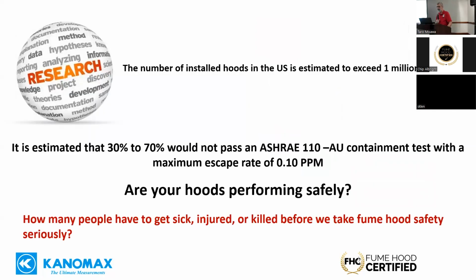So there's something in excess of 1 million hoods installed in the United States. And different people have made guesses. EPA did a little bit at one time, but it's estimated that 30% to 70% of that million hoods would not pass an ASHRAE 110 as-used containment test with a maximum escape of 0.10 parts per million. So there's a lot of hoods out there that unfortunately don't work.